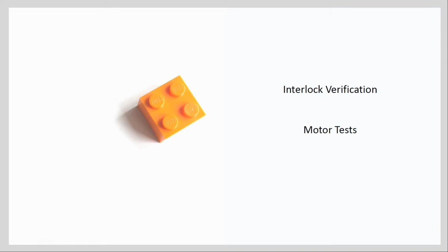Essentially, what this would be is a truth table to verify that if this one's closed and that one's closed, then this one must be open. And you want to go through all the different configurations in that truth table to confirm that all interlocks are functioning correctly before applying any power to the system. If you do encounter any issues during your interlock testing, then you're going to want to get that rectified before moving on to the next stages of the tests.